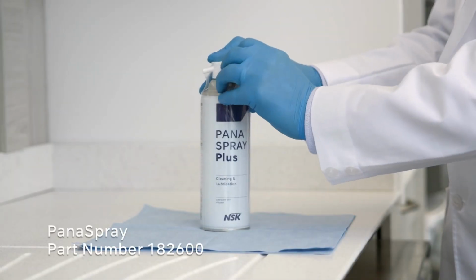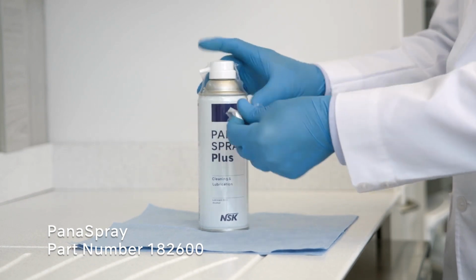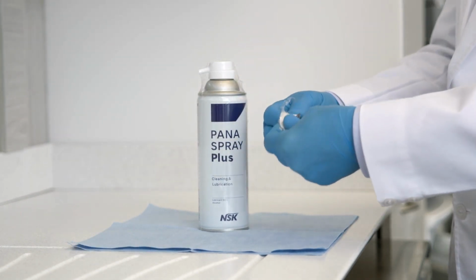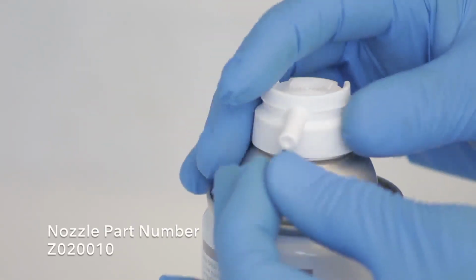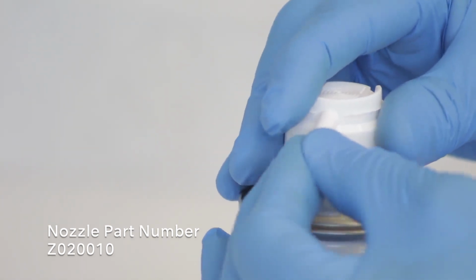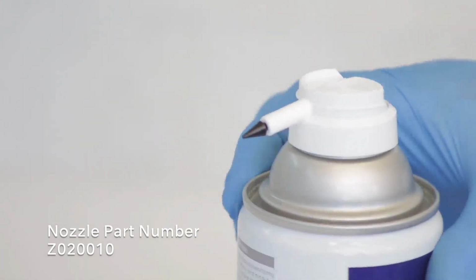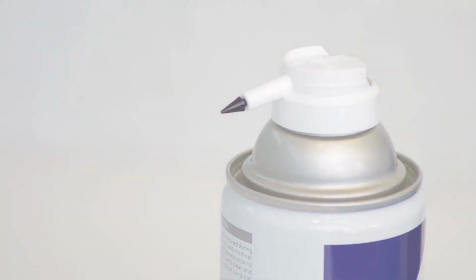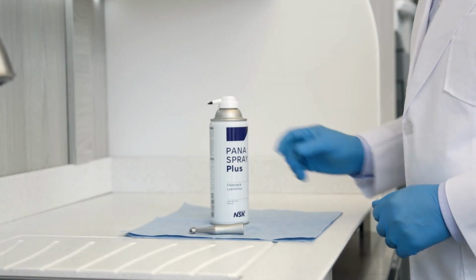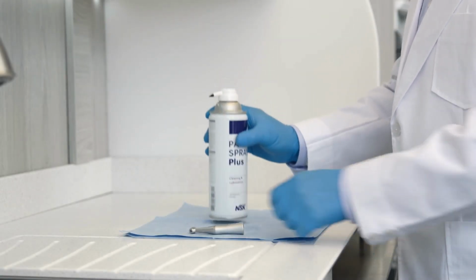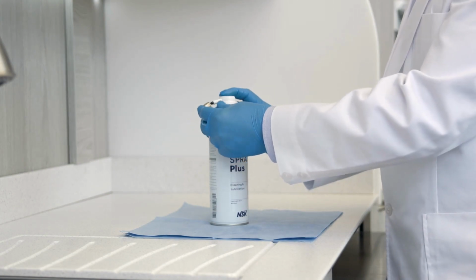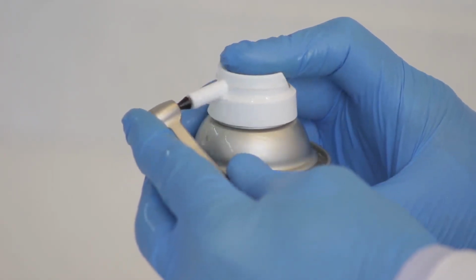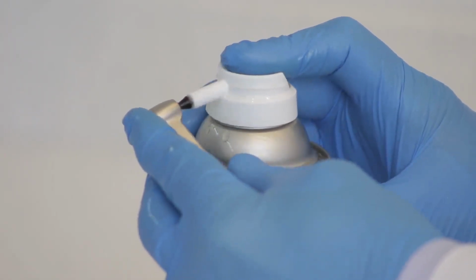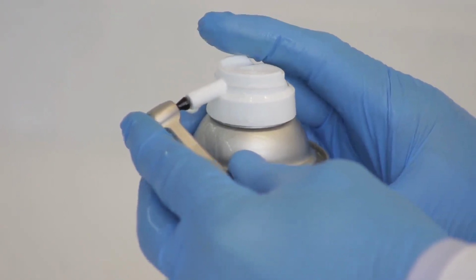Mount the spear-shaped nozzle that comes along with Panaspray and leave it on. If it's missing, you can order the nozzle using part number Z020010. Shake the can 3 to 4 times. Hold the can in an upright position. Insert the nozzle directly into the chuck and spray for 2 to 3 seconds.